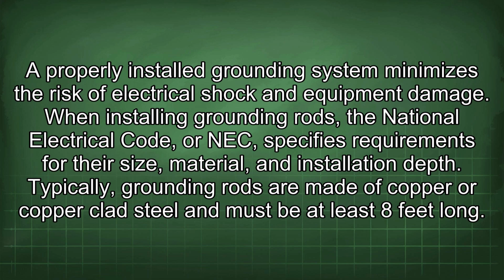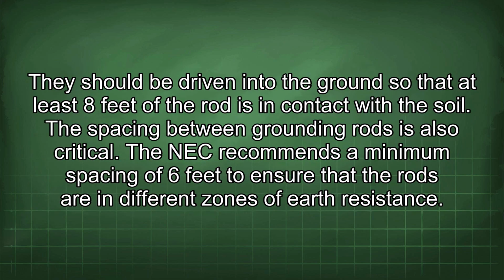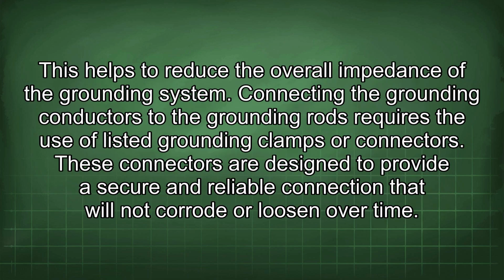When installing grounding rods, the National Electrical Code, or NEC, specifies requirements for their size, material, and installation depth. Typically, grounding rods are made of copper or copper-clad steel and must be at least 8 feet long. They should be driven into the ground so that at least 8 feet of the rod is in contact with the soil. The spacing between grounding rods is also critical. The NEC recommends a minimum spacing of 6 feet to ensure that the rods are in different zones of earth resistance. This helps to reduce the overall impedance of the grounding system.